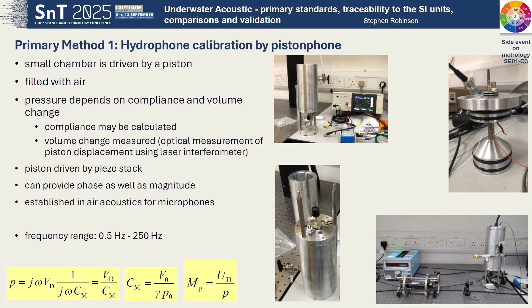The frequency range on this system, which we developed in the EU Infra EV project, goes from below 1 hertz up to 250 hertz, and you can see some pictures of the instrumentation there. We can calibrate hydrophones down, typically we only go down to 1 or 2 hertz, but this one goes down to 0.2 hertz. Over this range the hydrophone is flat, invariant with frequency, except for a low frequency roll-off due to the leakage resistance and capacitance, giving you a slight high-pass filter effect.